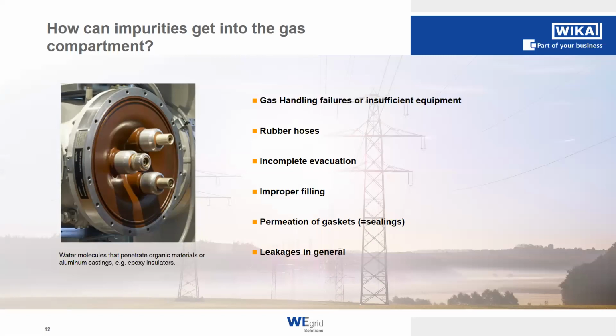One, the most simple one, is just handling failures or insufficient equipment, which is already damaged. We also have rubber hoses, which are connected to the gas compartment, and rubber hoses age with time, and through the aging, the rubber gets perforated, and the humidity can therefore creep into our gas compartment. Also, an issue could be incomplete evacuation. Therefore, I still have air or nitrogen within my gas compartment, which could already be saturated with water. Also, improper filling could be a reason, and the permeation of gaskets.